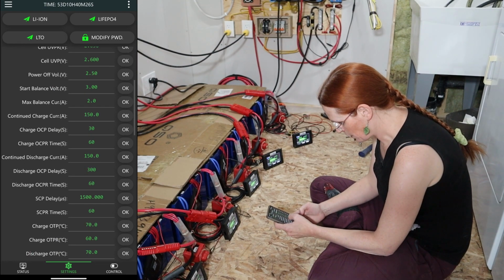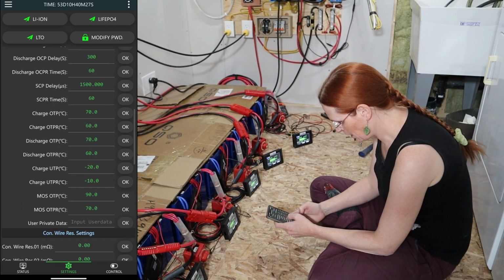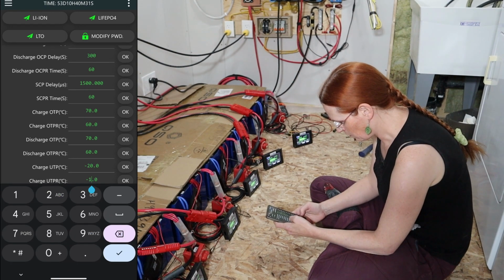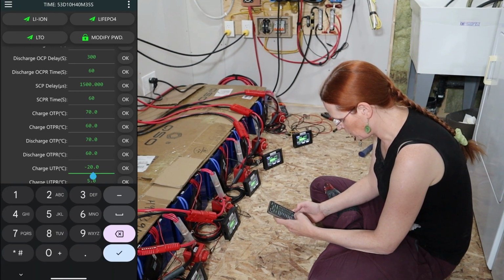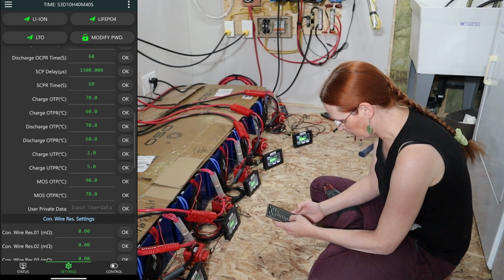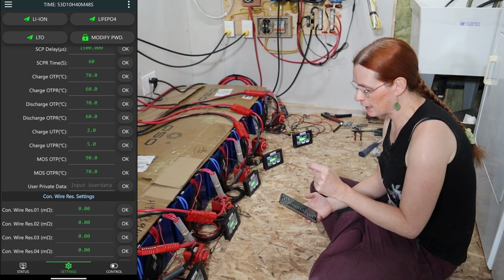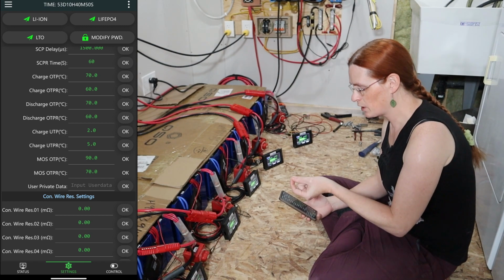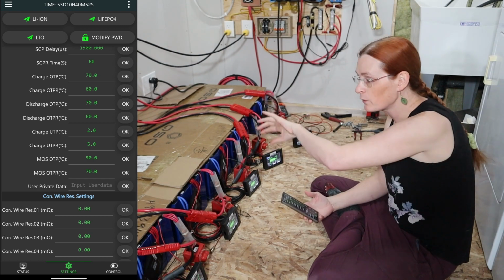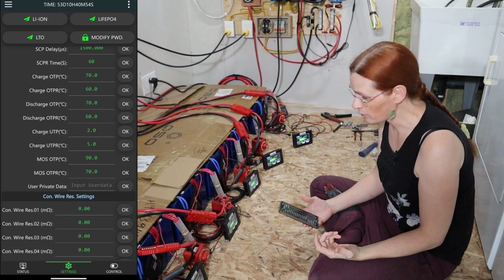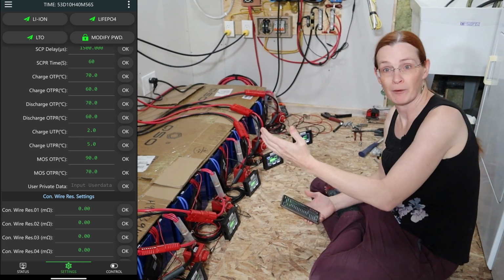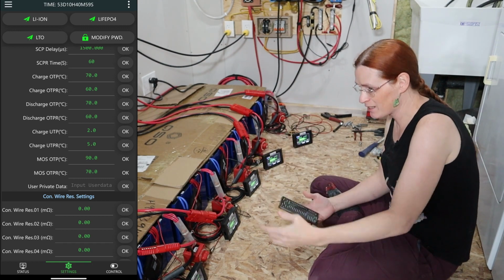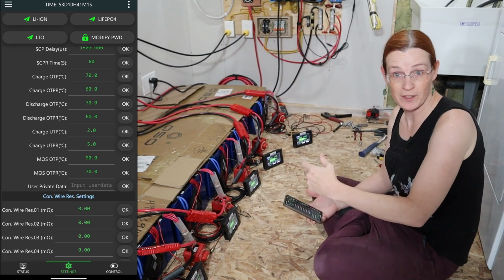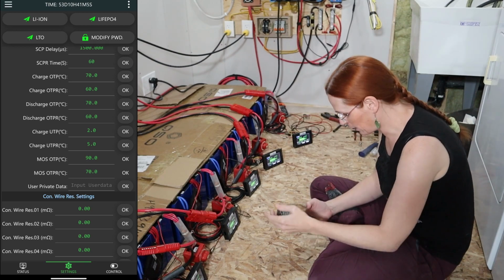Under voltage, I said was fine. I want the under temperature protection recovery to be 5 degrees, and I want the shutdown to be 2 degrees, just to give myself a little bit of a buffer. I want 2 degrees because I don't know where the temperature sensor is going to be. It won't be on the outer edges, it can't be, it's too short. So if I've got cold coming in from the outside, the outer packs might be getting close to freezing before the sensor knows it. That's my logic anyway.